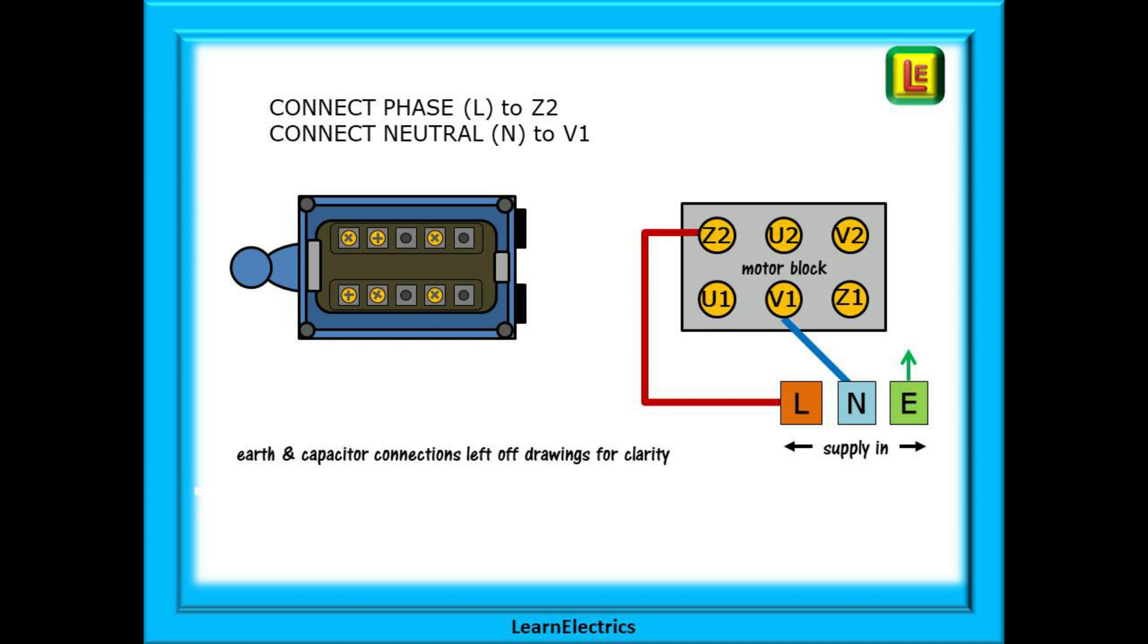An earth or CPC connection must also be supplied to the metallic parts of the circuit, the motor, the switch etc. But from this point on we will leave the capacitor connections off the drawings for clarity and we will also leave the earth connections off the drawings. But remember they are there in real life.